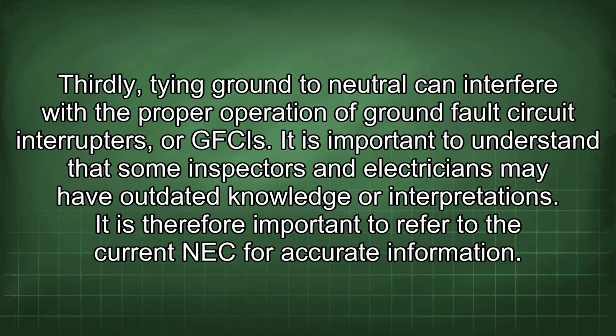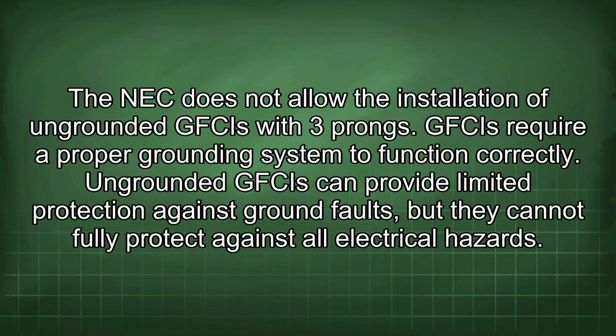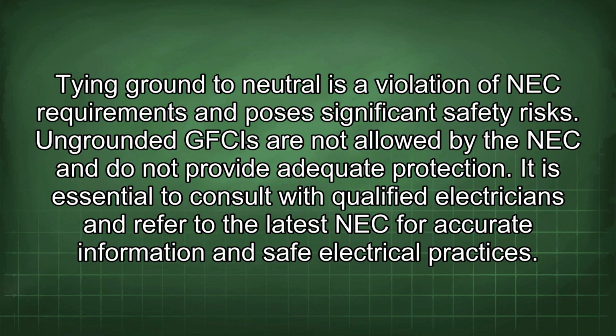It is important to understand that some inspectors and electricians may have outdated knowledge or interpretations. It is therefore important to refer to the current NEC for accurate information. The NEC does not allow the installation of ungrounded GFCIs with 3 prongs. GFCIs require a proper grounding system to function correctly. Ungrounded GFCIs can provide limited protection against ground faults, but they cannot fully protect against all electrical hazards. Tying ground to neutral is a violation of NEC requirements and poses significant safety risks. Ungrounded GFCIs are not allowed by the NEC and do not provide adequate protection.